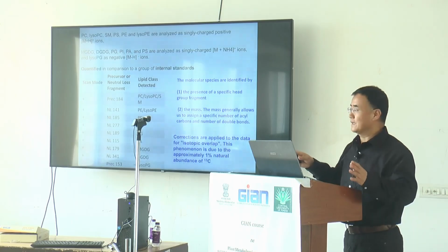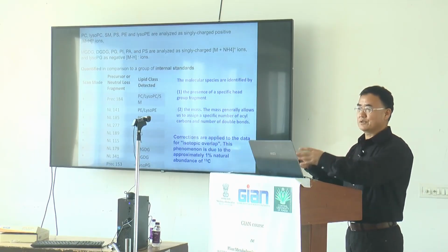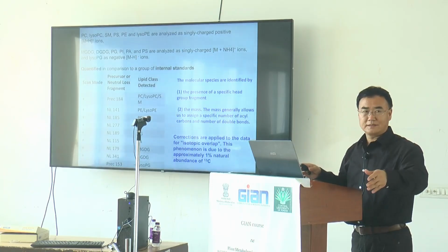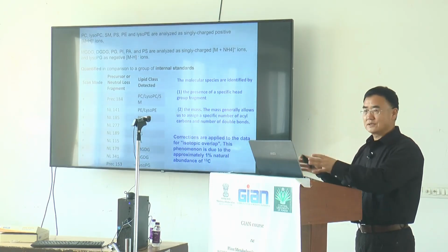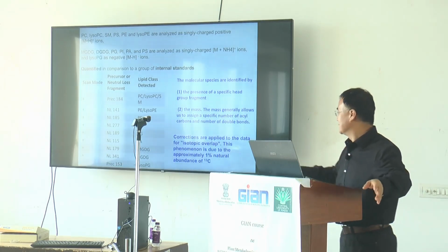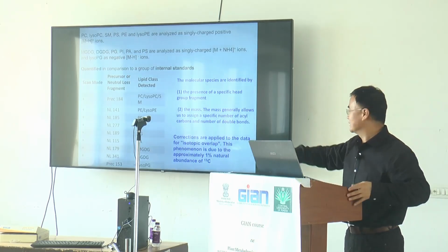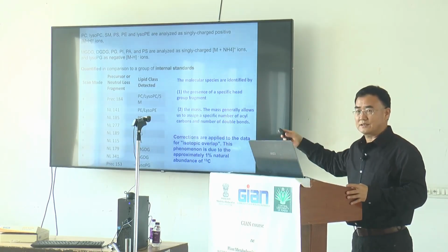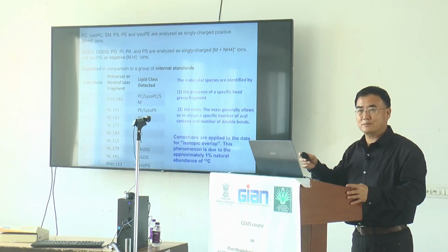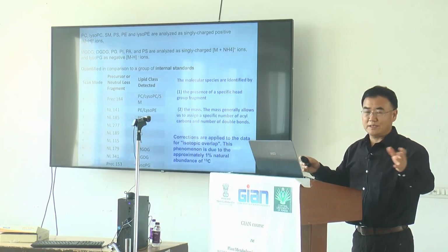Because every LCMS, commonly HPLC coupled with the mass spectrometry, you need to adjust the separation part and also the MS part, the mass spectrum part. So adjustment usually takes some time, you need to clean up, and then you readjust, using the isotope overlapping or other more accurate internal standard. Internal standard is much less cost effective, but you need to apply it.